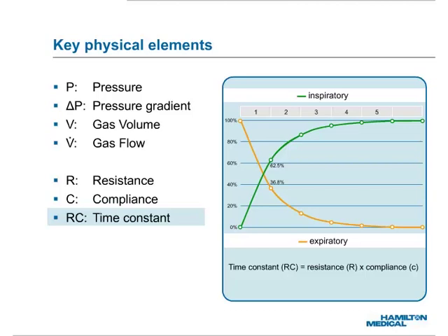The length of time required to complete a volume change varies, depending on clinical conditions. The question is: is there any possible way for us to know or estimate objectively and individually the required time to complete a course of volume change? Yes, the tool we use is the time constant. The time constant parameter is the product of the monitored compliance and resistance of a respiratory system. Therefore, the time constant increases when resistance and/or compliance increase.